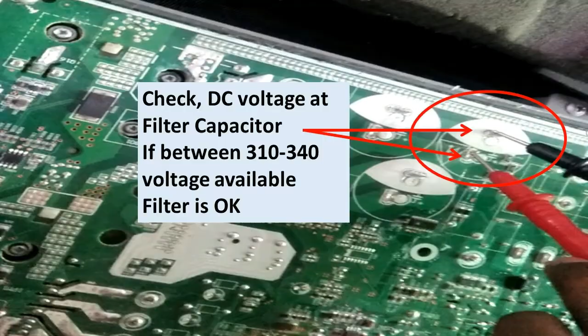Then we have to check the filter capacitor. There are 3 filter capacitors available in the PCB, for U, V and W, giving the filtered DC supply. So we have to check the DC voltage between the capacitor negative and positive points, and we have to check in all the 3 capacitors.